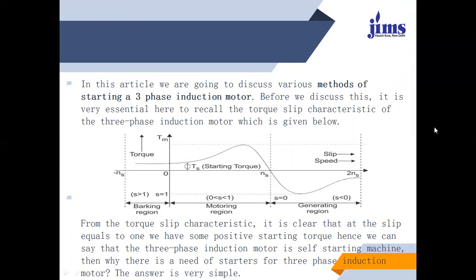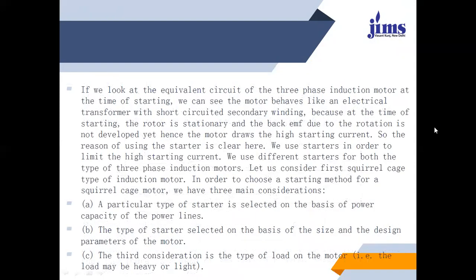Then why is there a need for a starter for a three-phase induction motor? The answer to this question is very simple. If we look at the equivalent circuit of the three-phase induction motor at the time of starting, we can see the motor behaves like an electrical transformer with a short-circuited secondary winding, because at the time of starting the rotor is stationary and back EMF due to rotation is not yet developed. Hence the motor draws a very high starting current at that moment. So the reason for using a starter is very clear: we use starters in order to limit the high starting current.